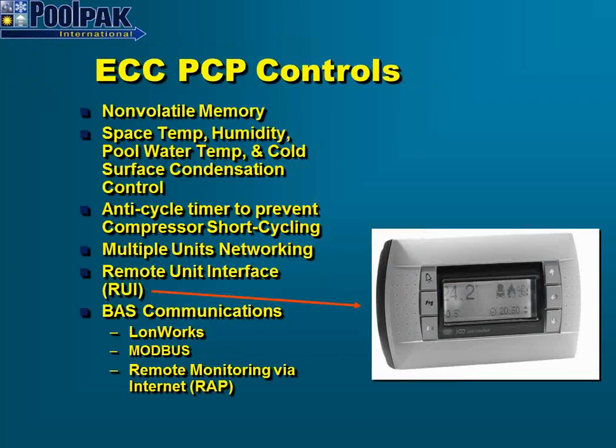The controller, pretty powerful actually. It's as simple or as complex as the situation requires. Non-volatile memory, so if you suffer a power outage, your settings will still be in the unit. You can control space temperature, humidity, pool water temperature, and also reads your cold surface condensation sensor.